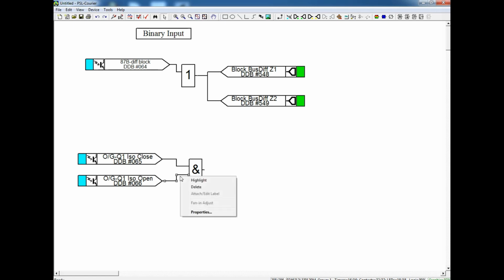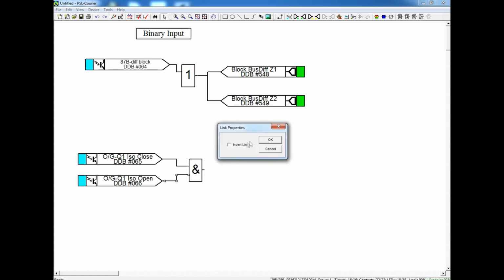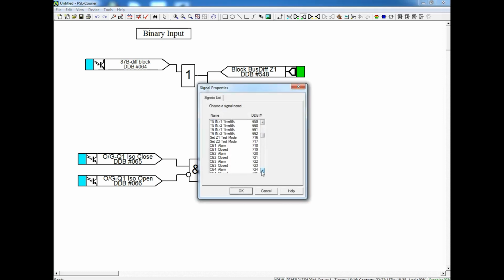For our close status, if you see, why I am taking this open also is to reduce the maloperation. For this I am taking an AND gate and I am making this open as an invert. That means when we get the close status, the open will be 0. So the invert will make 1. So the AND will get satisfied. It will reduce the maloperation.